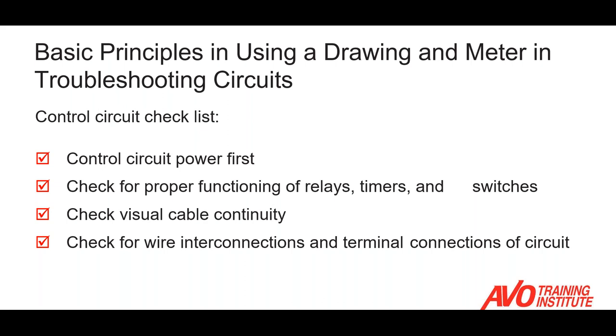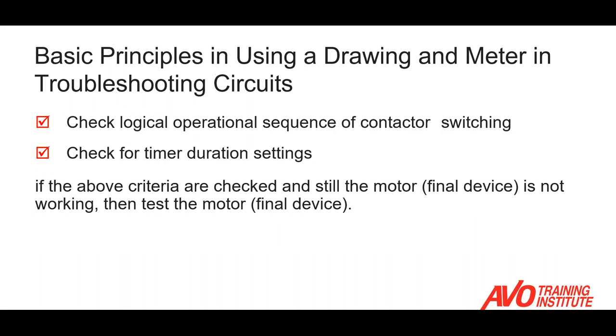When we're looking at the control circuit, we first check the control circuit power — do we have available potential? We want to check our devices: relays, timers, and switches, and make sure they function properly. Check cable and wire continuity, and also check our wire interconnections and terminations. We need to check the logical operation sequence of the contactor switching, and verify the duration settings of any timers to make sure they're set correctly. If we check all the above criteria and the motor is still not working, then we test the motor — that's the final check we do.